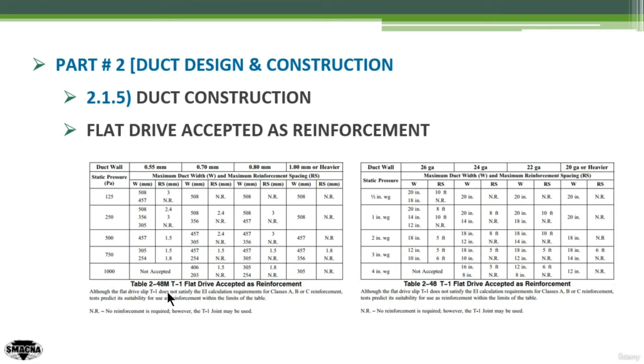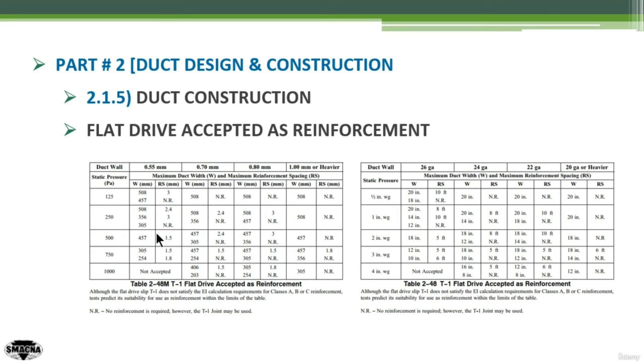This table also has some notes. Although the flat drive slip T1 does not satisfy the calculation requirement for classes A, B, and C reinforcement, tests predict its suitability for use as a reinforcement when the limits of this table are met. NR means no reinforcement is required; however, the T1 joint must be or may be used.